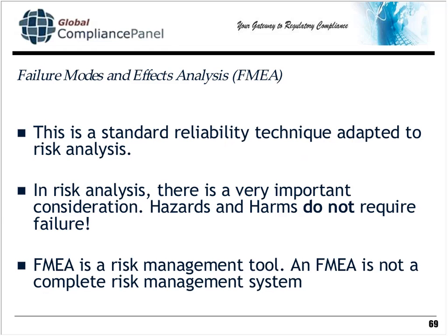Now, I'm going to warn you again. Very often, people make the mistake that they should be analyzing failures instead of hazards. And remember, hazards can occur in both normal and fault conditions. So if you analyze only failures or fault conditions, you're missing some significant portion of risk in your medical device. And what often happens is that people use the FMEA, which is a tool to help you with hazard analysis, instead of doing the hazard analysis. So they mistake the tool for the technique that they're supposed to be using.